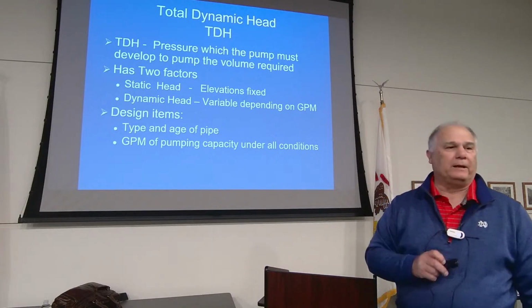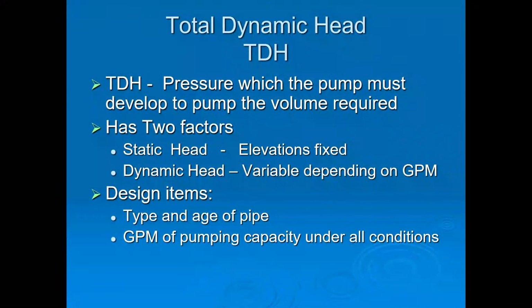So we talk about TDH. In TDH, there are two conditions that we have to worry about. First is static. Once we put the pipe in the ground, static is static. It's not going to change. The second one is dynamic. The dynamic is going to change based on the amount of water we're pumping through that pipe and the type of pipe. Pretty simple explanation.